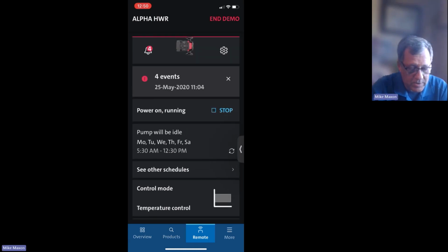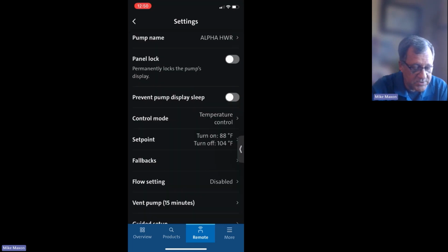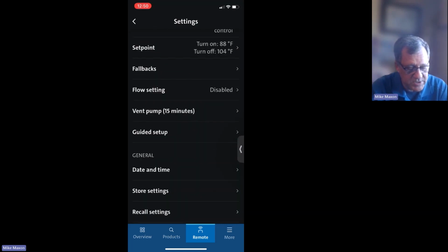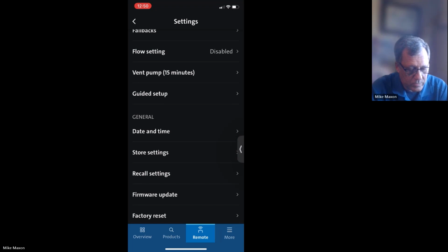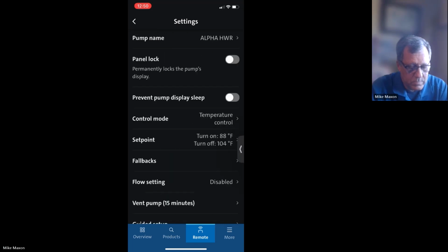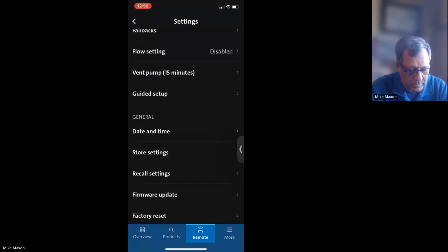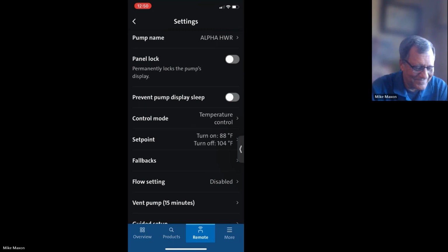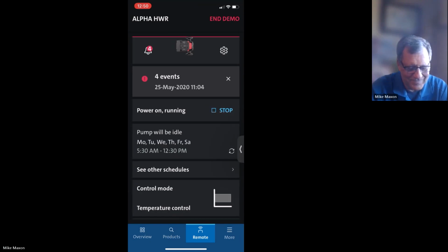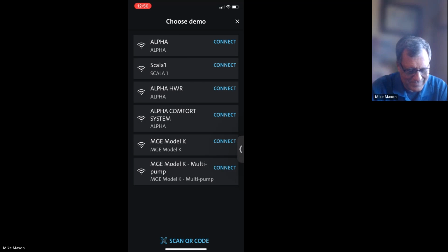The little gear in the corner is your settings. That takes you to some more set points that you can change or see. At this point, if you always set up the same pump, you could store your settings, and the next time you go to another setup, you could just recall that setting and pop it right in and be done. And you do have the best thing in the world at the very bottom. Factory reset? Factory reset, yes. So basically it means you can play with it, and if you screw it up, you can return it back to the original factory setting. So it's always great to have that there.